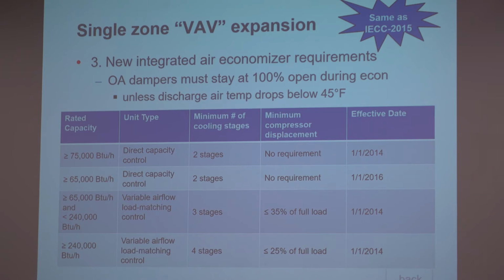And so that sort of drove this change to have more compressor stages. If you have more compressor stages, then when you bring on that first stage, it's smaller and it's much less likely to cause this sort of control interaction that's meant to protect the equipment and also the comfort of the occupants. If you have a space that has critical humidity requirements, 45 saturated, that bring humidity down versus coming off 53 saturated or something like that.